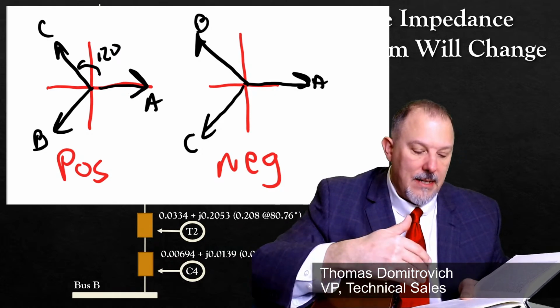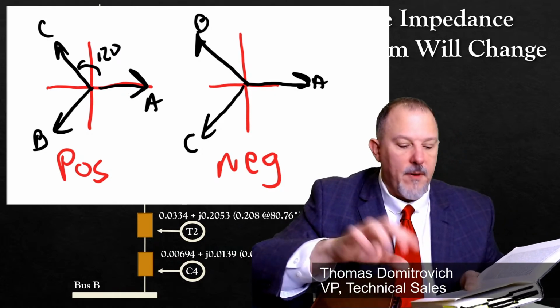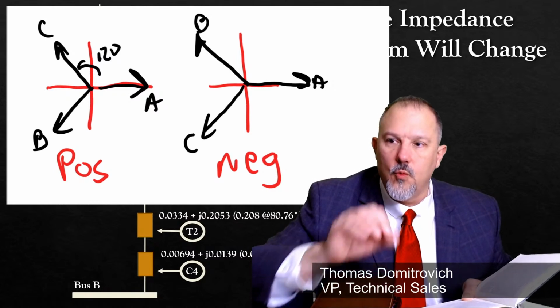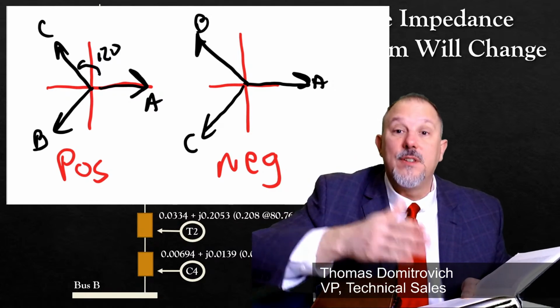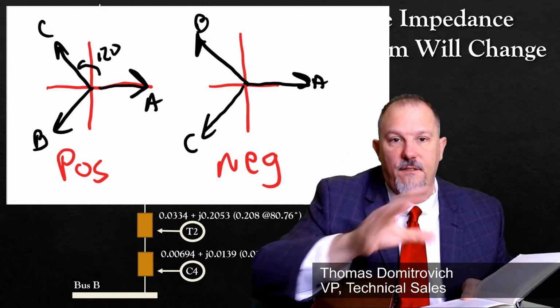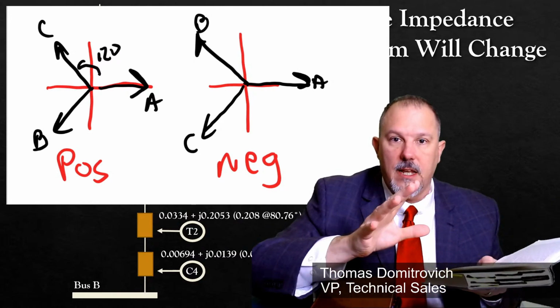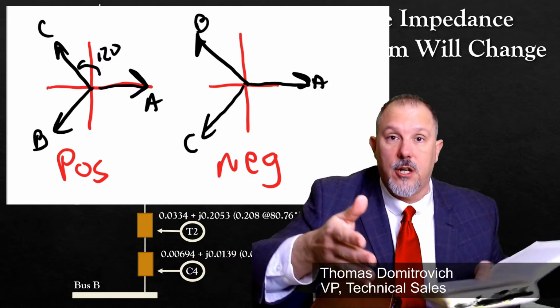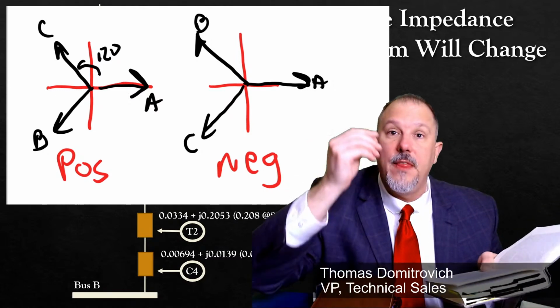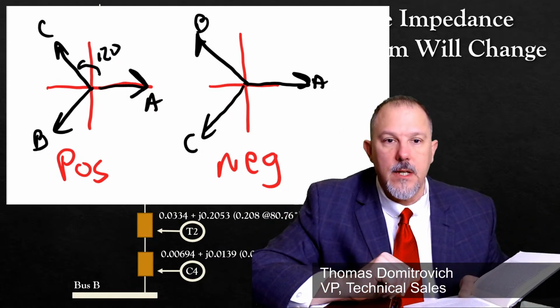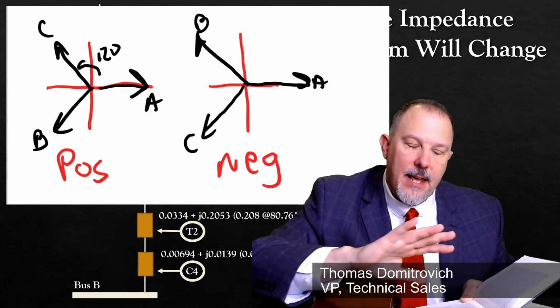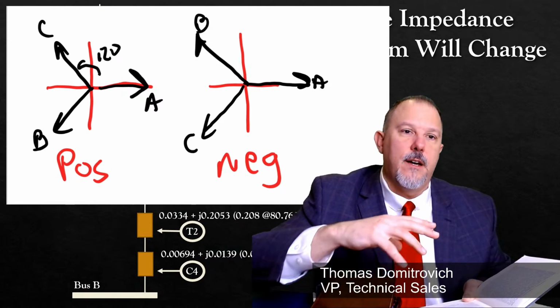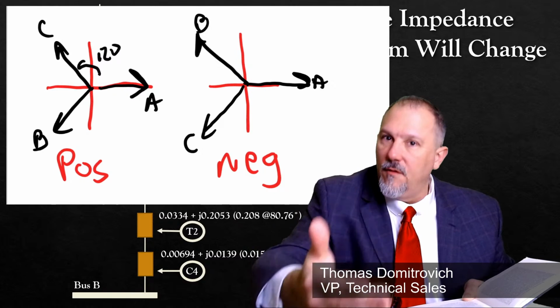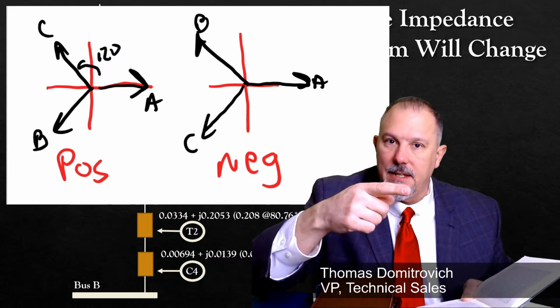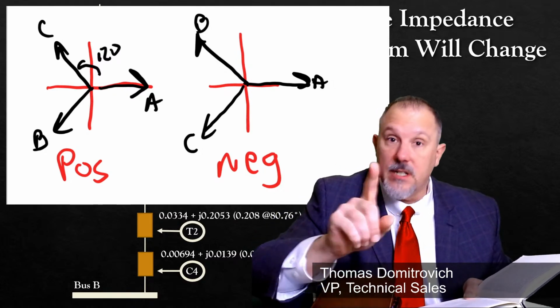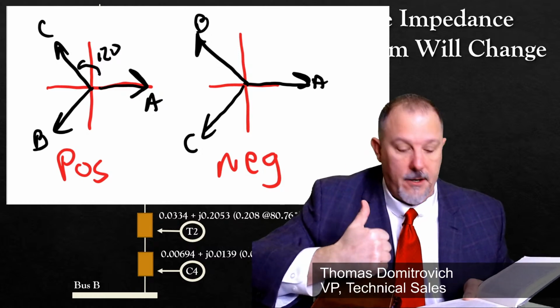Fortescue brought to the table, and others brought to the table, but Fortescue, I think, is probably the first one who really got it out there, the zero sequences, where they're not out of phase with each other. They're not rotating like that and out of phase. They're all in phase with each other because they're all going to ground and they all add. And they recognized that since they're all in phase with each other, they won't flow through a delta. They'll circulate in the delta, and we'll talk about that because that's important in creating our impedance diagram.